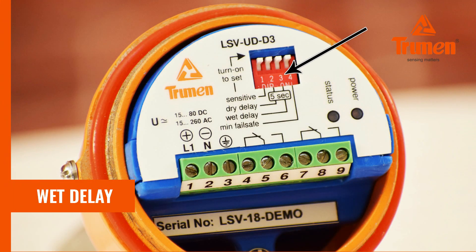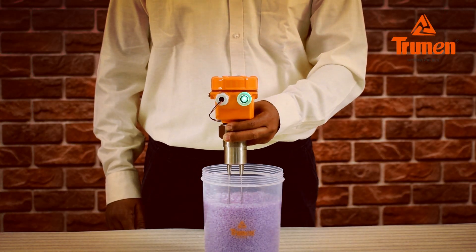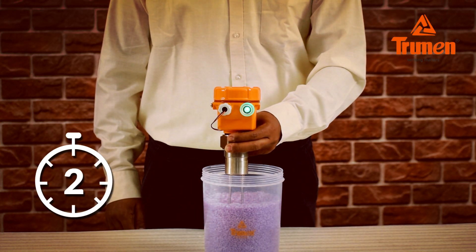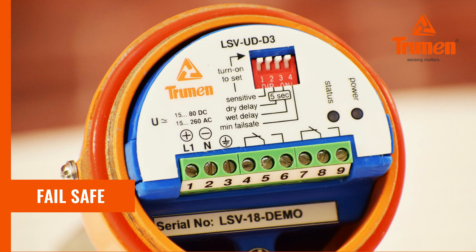Wet delay is set via dip switch number 3 — turn on switch 3 and fill the material; the LSV waits for 5 seconds before generating switching. Fail safe is set via dip switch number 4. When the sensor is installed for high level, keep dip switch 4 off — fail safe high or maximum. When the sensor is installed for low level, keep dip switch 4 on — fail safe low or minimum.